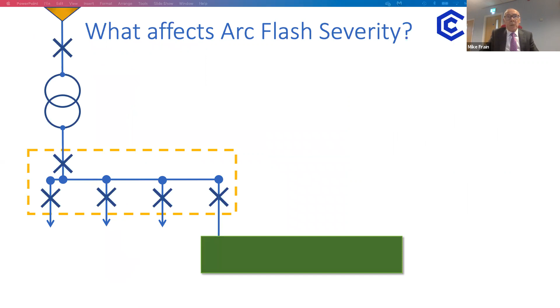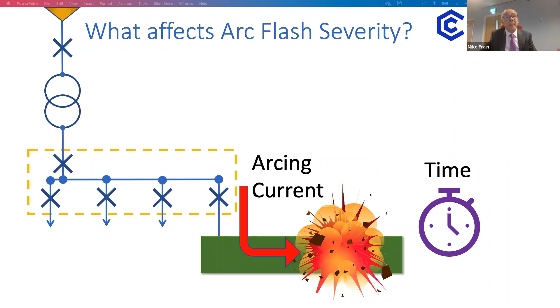So what affects arc severity? Well, the first thing is arcing current, and that is governed by the impedance of the supply source. The next is time, and this is the time that it takes for the protection systems to recognise a fault and also to disconnect it. In both cases, severity is directly proportional. So if you double the current, you double the incident energy. If you halve the time to trip, then you halve the incident energy, and so on.